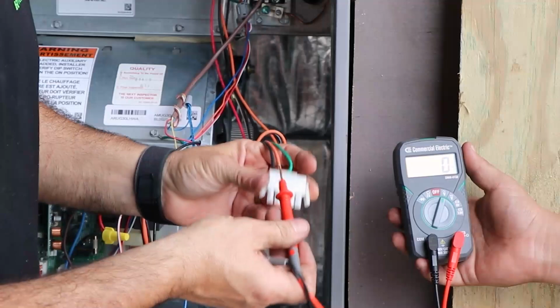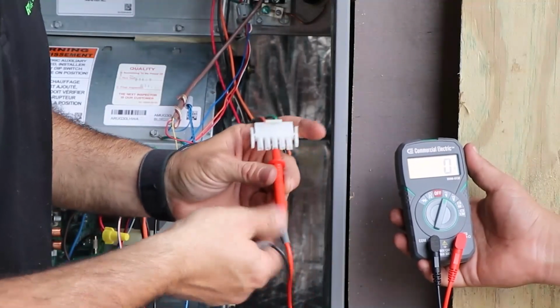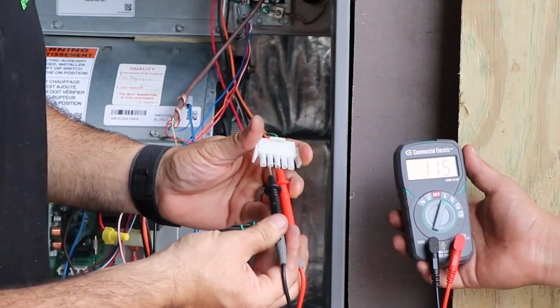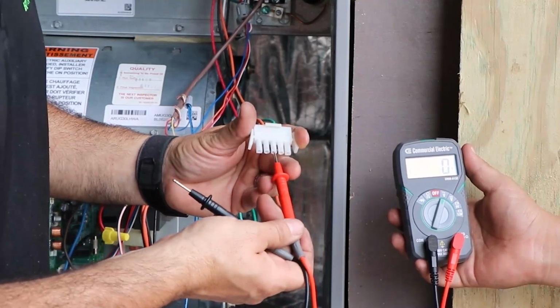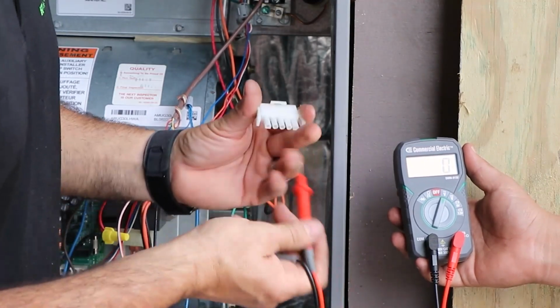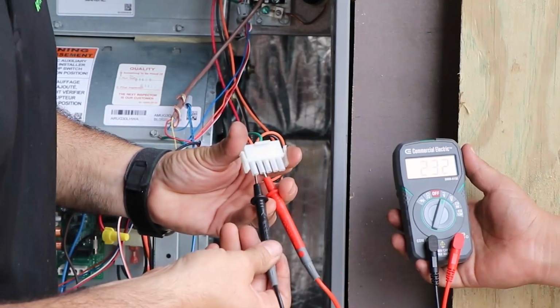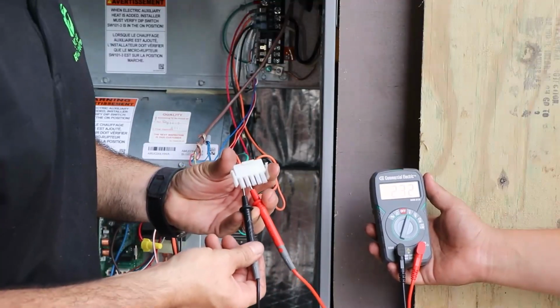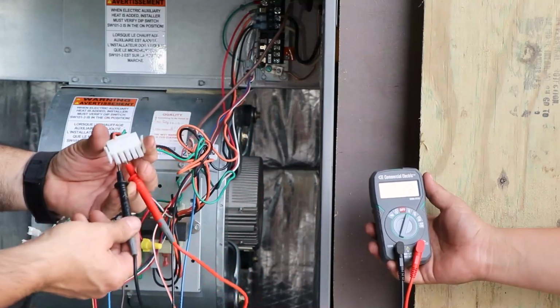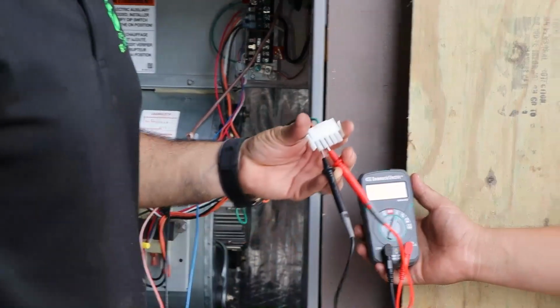So we're going to test between this green wire and this orange wire here. In this case, we get 115, which is correct. Now we're going to test between the green wire and the black wire. We get 117. We're going to test between the orange wire and the black wire, and we get 232. So on a 220 motor, you're going to have anything between 215 volts to 245 volts that is correct. So this high voltage harness tests out correct for 220 volts.